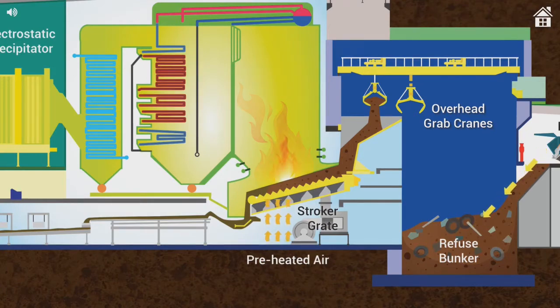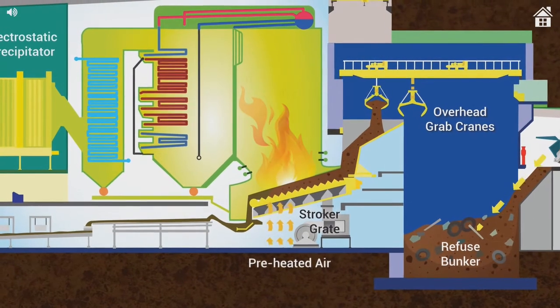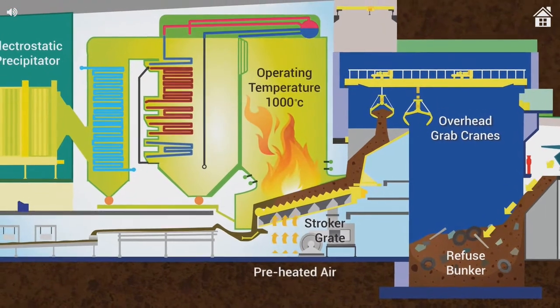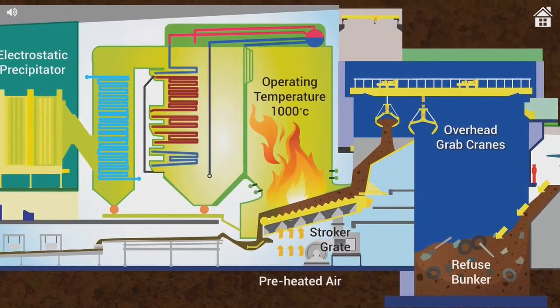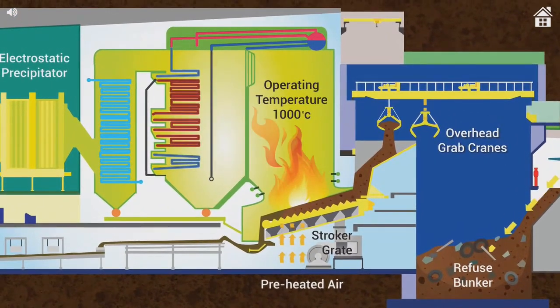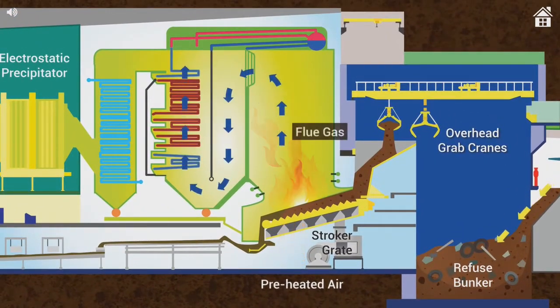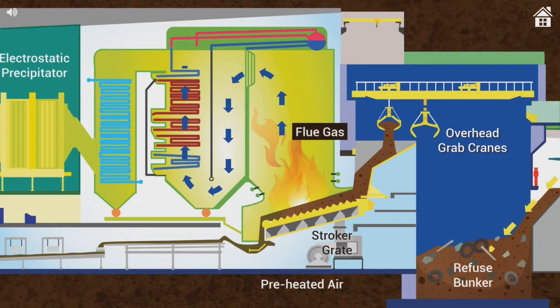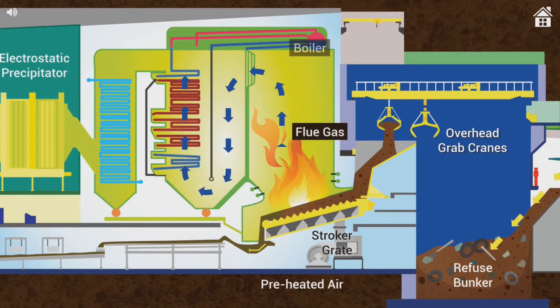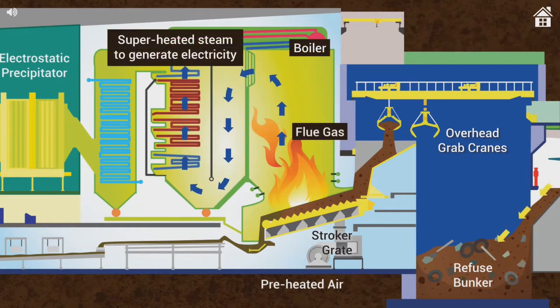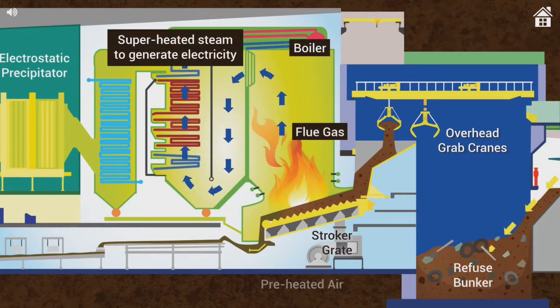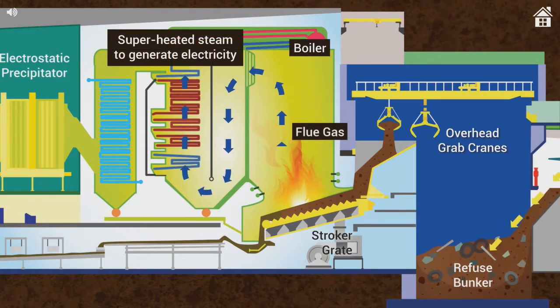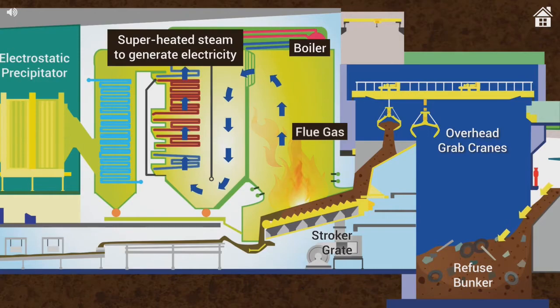The normal operating temperature in the furnace is about 1000 degrees Celsius. The flue gas produced in the combustion process flows through the boiler to generate superheated steam which is used to generate electricity.